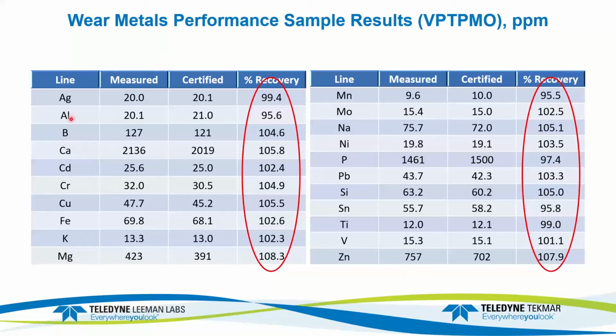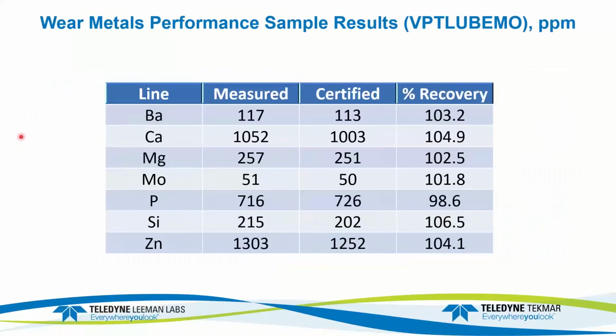So this is good. This is for all the elements, so these generally have various concentrations. And there is also a sample for the really high concentration elements or the additive elements. So we can see those recoveries are again right around 100%, which is what we expect. So we've been able to show that, even though we've increased the speed and we're doing some things with the pump and everything, there's really no effect on accuracy, which is what you would expect.